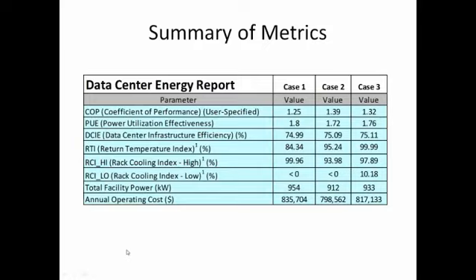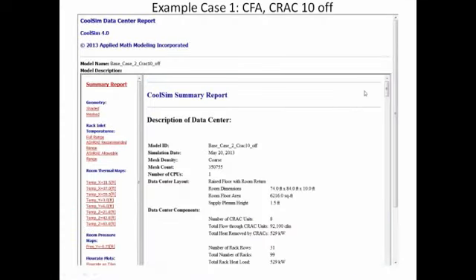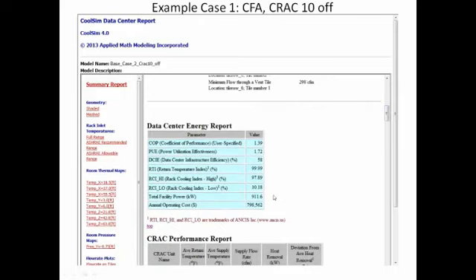So Paul, if you go back to that summary table. Yeah. The PUE. Yeah. Share the summary table, I just want to point out something with the metrics there. Yep. So really, and I think that attendees realize now where this is going, and where it's going is actually that RTI and RCI high and RCI low, there's like an interplay between these metrics. That's correct. The trick here is to get them as close to 100% at the same time. Right. So CFD is a fantastic tool of doing that without taking any risk in the data center. That's correct.